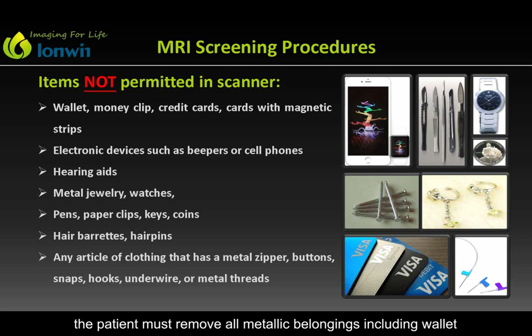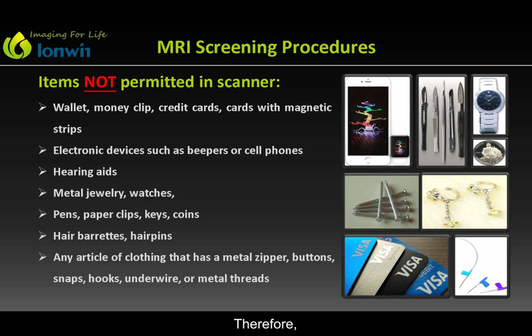Before entering the MRI system room, the patient must remove all metallic belongings, including wallets, cards, watches, pocket knives, and jewelry. Besides being attracted to the magnetic field of the MRI system, objects such as cell phones, hearing aids, and beepers may be damaged. Therefore, these objects are not permitted into the MRI environment. Any equipment to be used in the MRI scanner room must be MRI safe or MRI conditional, and all equipment must be appropriately assessed prior to use in the scanner room. So, how can we determine if items are ferrous? Ferrous metal detectors or test magnets may help indicate whether equipment is ferromagnetic, just like these.